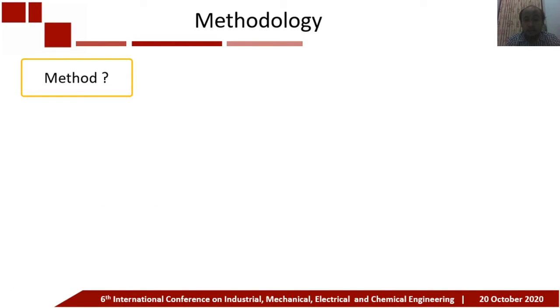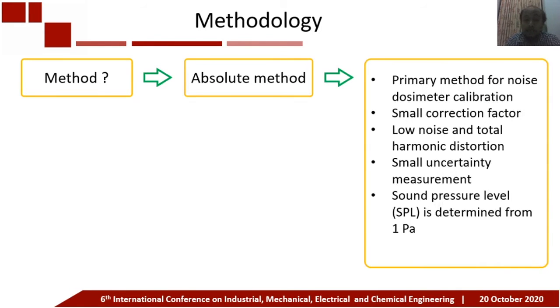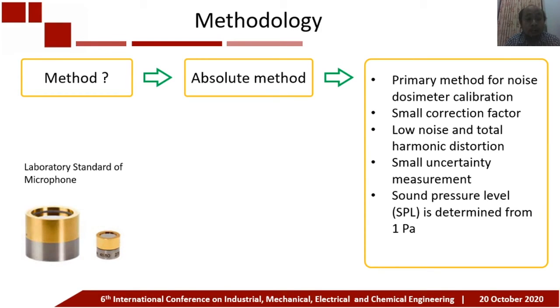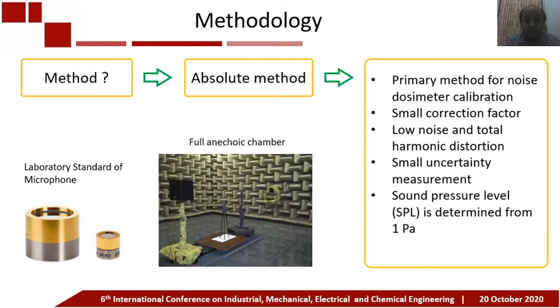The method used in our research is the absolute method, which is considered a primary method for noise dosimeter calibration, having a small correction factor, low noise and total harmonic distortion, small measurement uncertainty, and can produce a sound pressure level derived from 1 Pascal. To realize it, we need a laboratory standard microphone as the primary standard for acoustic measurement and calibration, and a full anechoic chamber.